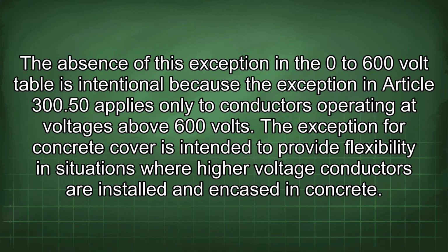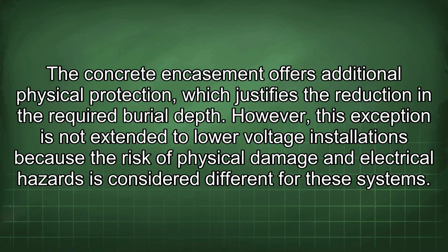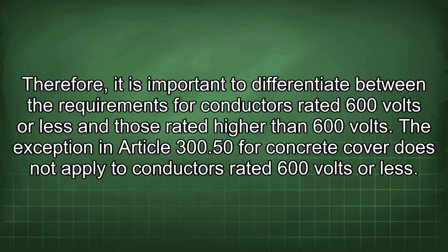The exception for concrete cover is intended to provide flexibility in situations where higher voltage conductors are installed and encased in concrete. The concrete encasement offers additional physical protection, which justifies the reduction in the required burial depth. However, this exception is not extended to lower voltage installations because the risk of physical damage and electrical hazards is considered different for these systems.